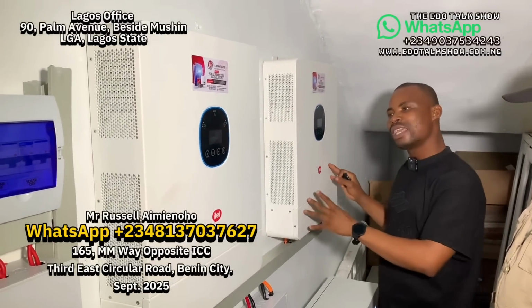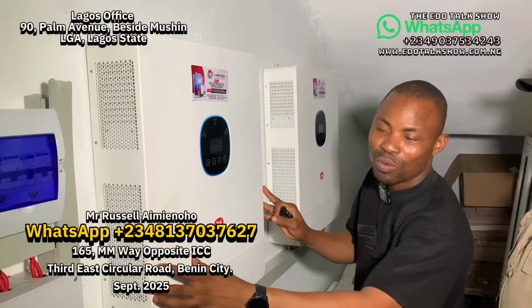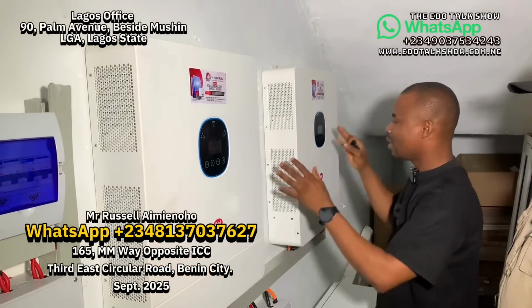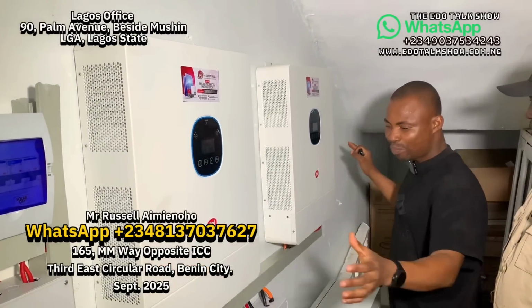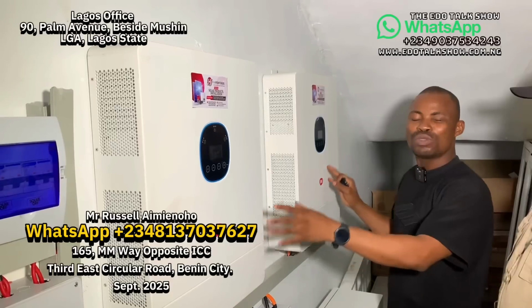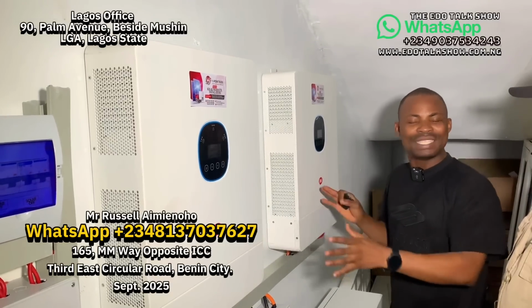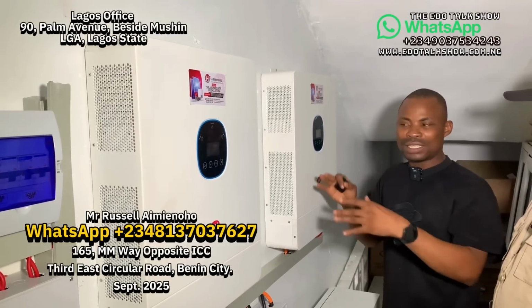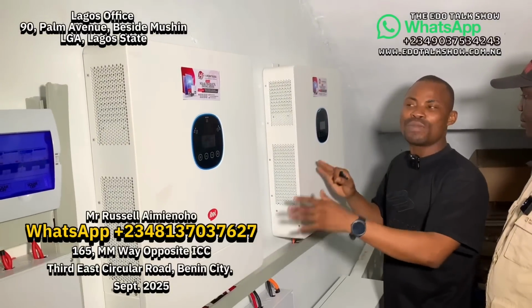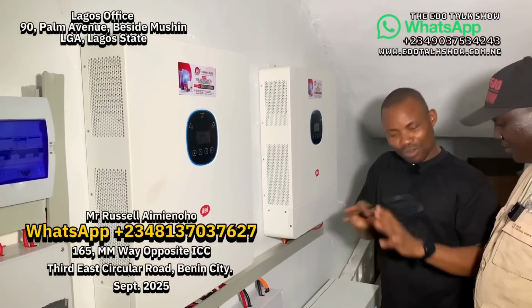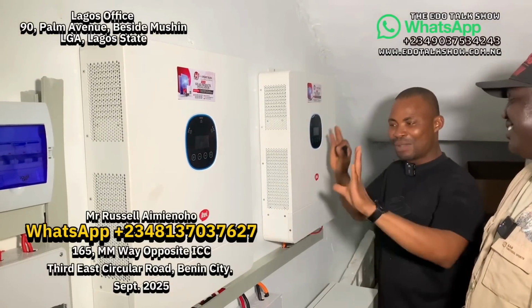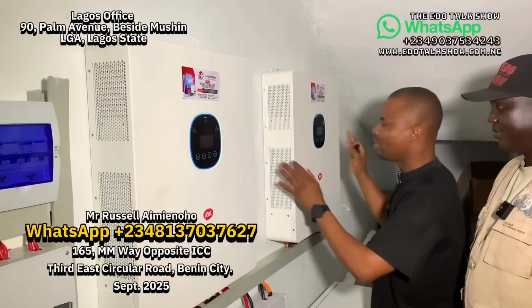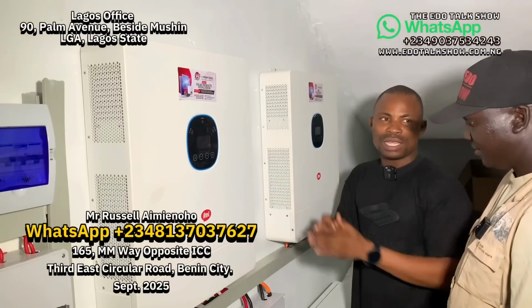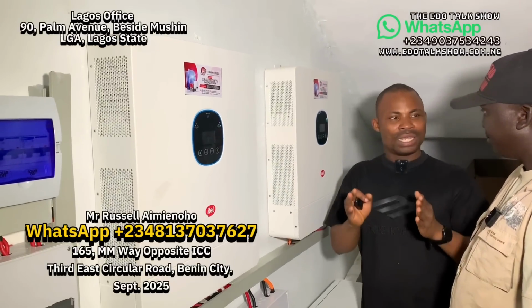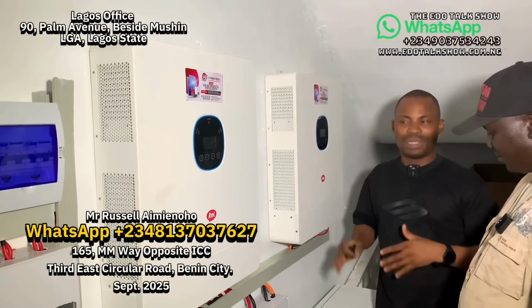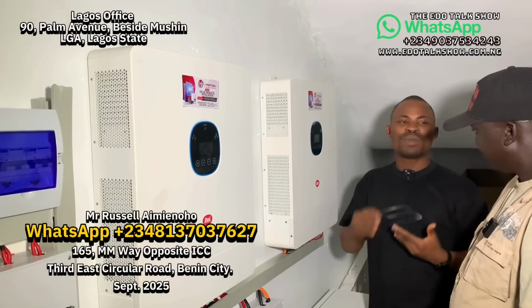And what we do here, as this inverter is 12 kilowatts, which is 14 kVA, and this one is 12 kilowatts, 14 kVA, we program them together. Two of them can become 24 kilowatts, which is 28 kVA. But for the starting current of the two inverters, it can be 48 kVA. But I want to explain that one for you to understand. You all know this one is 12 kilowatts and this one is 12 kilowatts. We merge the two together, supplying the same load. They became one inverter. But as we talk, I will explain them one by one.